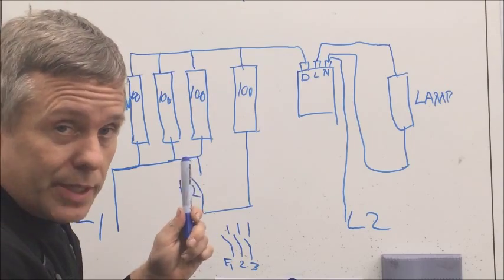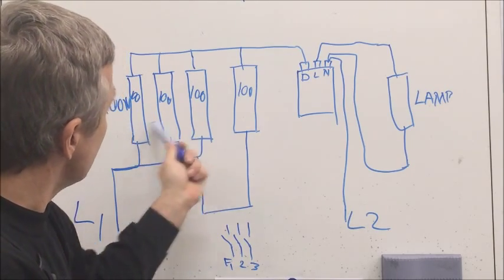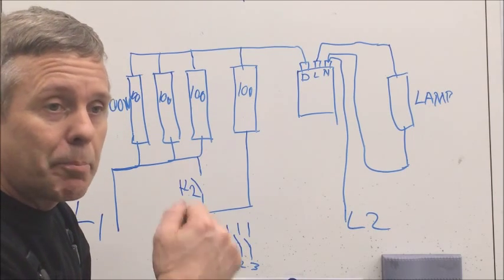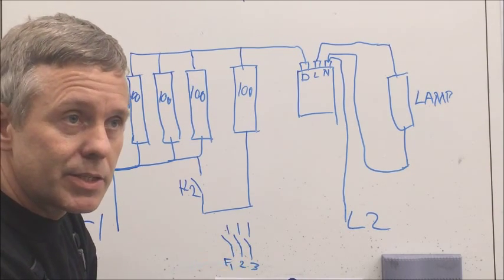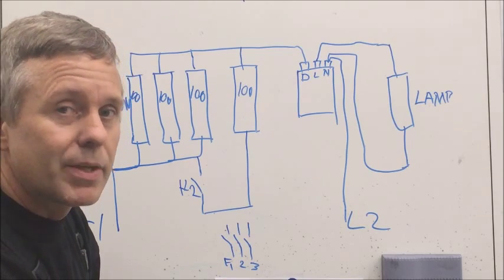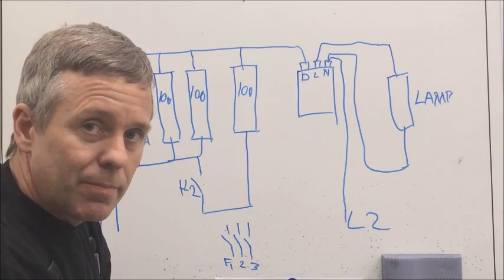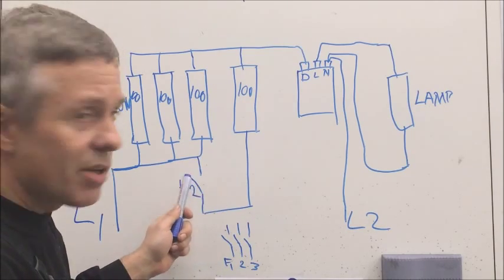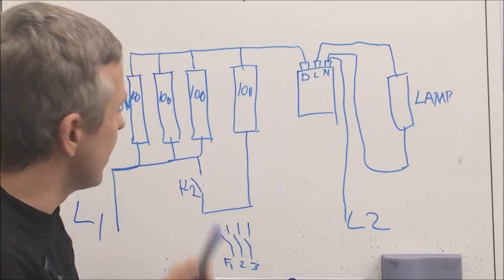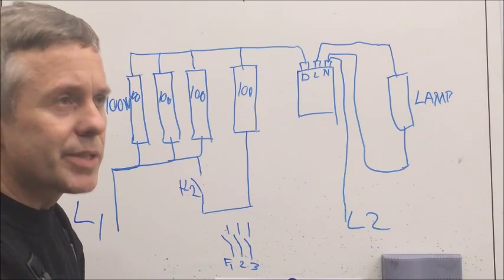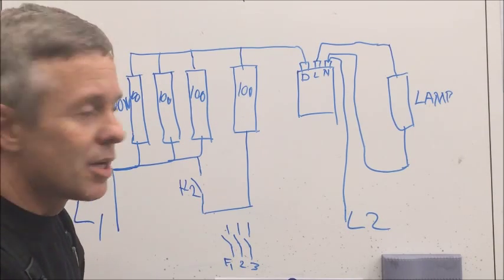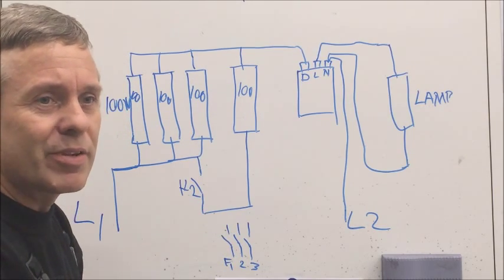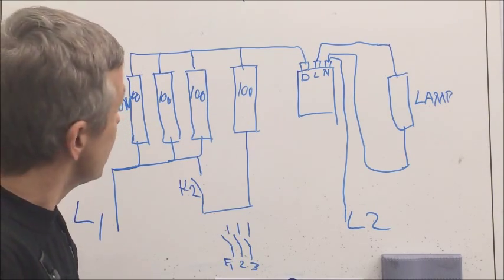So, what's important, though, is that it starts up on the full 400. You want to have a powerful ignition of the lamp. So, it won't char. And that's why it's important that sometimes, if this contactor goes bad, it will never turn up and down, of course. But also, you will have a shorter lamp life because it's not igniting as powerfully as it should.